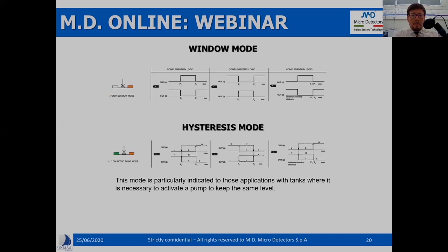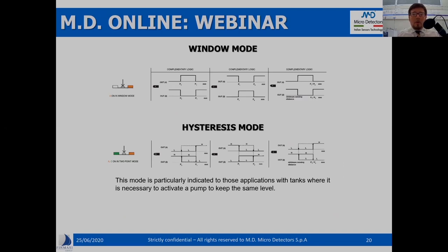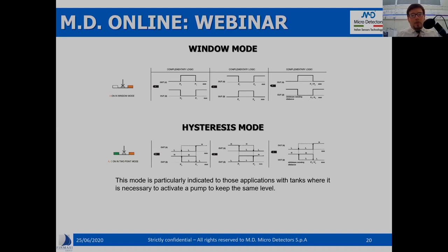Let's explore them. The first selection is the window mode — we have two outputs working within a window of two points. The interesting thing is these two outputs work as complementary outputs: one works in normally open mode, the other in normally closed logic. So within the window, the first will be equal to 1 and the second equal to 0. The second choice in the menu is the hysteresis or two-point mode, important for tank applications — for instance, to control a pump that maintains a constant level within a tank.